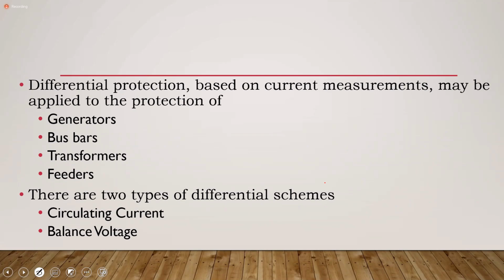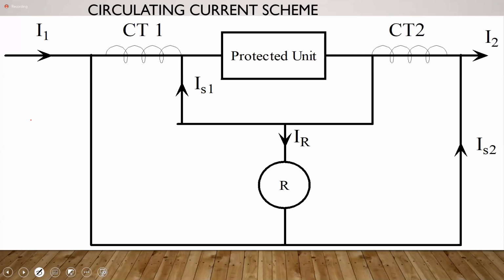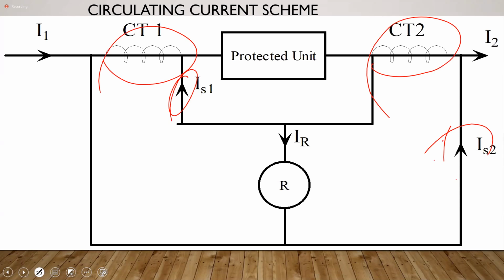You have the circulating current, you have the balance voltage. The balance voltage is what we use for things like your feeders. The circulating current we use for generators, bus bars, and your transformers. Okay? In more detail, that's what we have here. So you have CT1, you have an output. CT2, you have an output. These two outputs are compared, and the difference gives you the relay current. That relay current goes beyond a certain preset value.